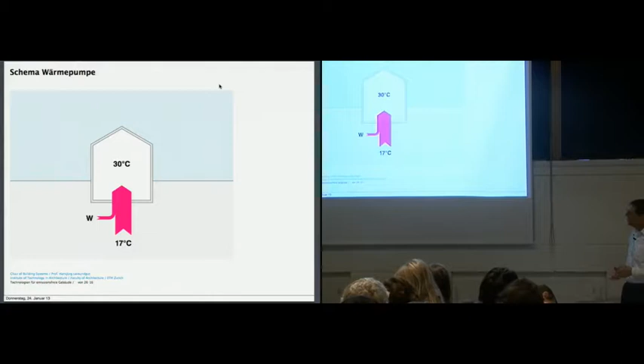The higher up you go, the more energy you mix into the system from the soil, and here is a temperature difference the machine has to lift. That pumping up means augmenting the temperature - that's the temperature lift. If you have a zero here, you get infinity. That's due to the formula.